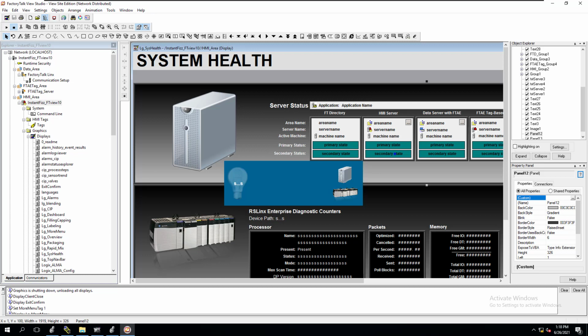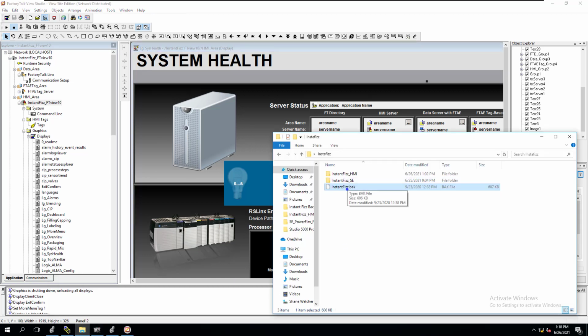You can take it and use this import process, use this restore process that we did right here using the FactoryTalk admin backup file, use that and then come back and just reconstitute your actual HMI application and get it fully working within a short time frame. Again, make sure you go through the application afterwards and do your due diligence and testing and making sure all that works. But this is effectively the best practices on how to restore an HMI application.